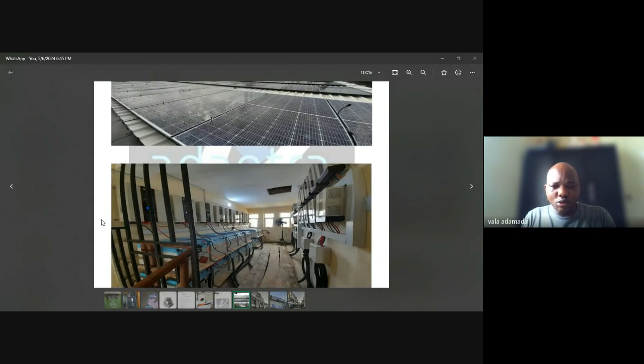So once they are communicating, the excess current we would have had trouble with, remember 20 kVA requires a lot of current, is shared between the two inverters, and the output is matched together to achieve that 20 kVA. So you see, this is what they have actually achieved.